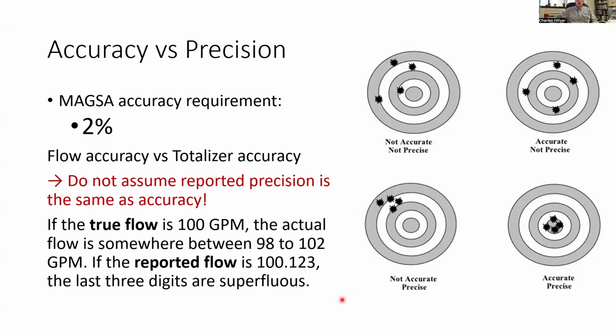Also, it's important to note that the precision of the reported flow should be appropriate for the accuracy that the meter has, but it isn't always. This happens on websites that report flow, where the math being done on the website just displays the result without trimming the extra digits on the end. So for example, with 100 gallons per minute and 2% accuracy, if the reported flow is 100.123, those last three digits are really superfluous because the accuracy is more coarse than what these digits imply. So if you're seeing flow meter data on a website or on your cell phone with a whole bunch of extra digits at the end, don't assume that those are absolutely correct, because in general, they're not.